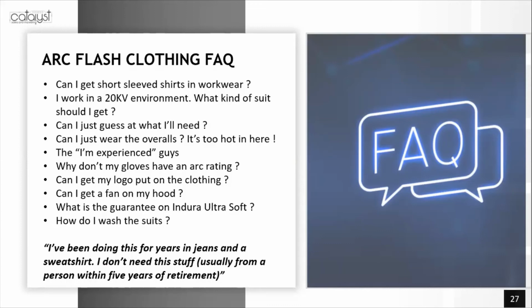Can I just guess what I need? No, you can't guess. Can I just wear the overalls, it's too hot in here? No, you can't just wear the overalls — you're only protected as your least protected area. So say I've just got the overalls on and they're rated 40 cal, my overall rating is still 0 because I'm only as protected as my least protected area.